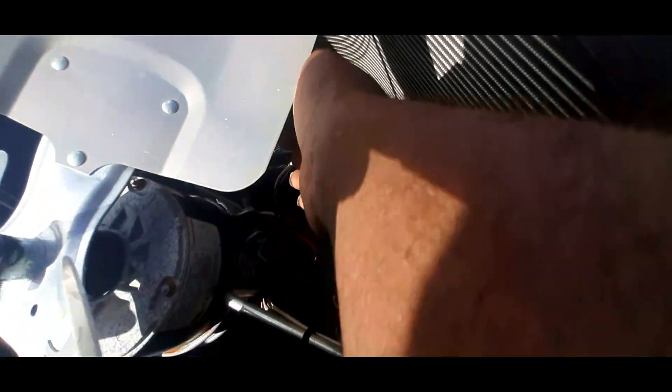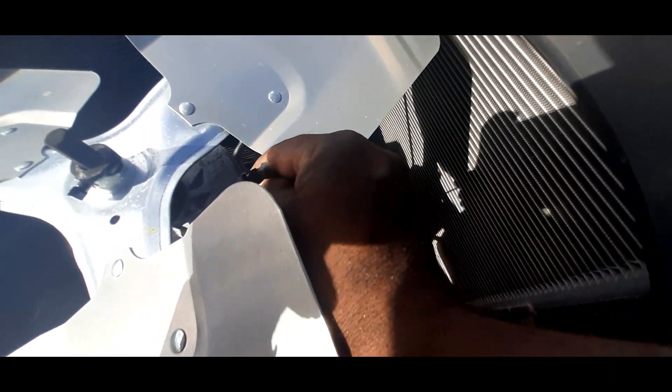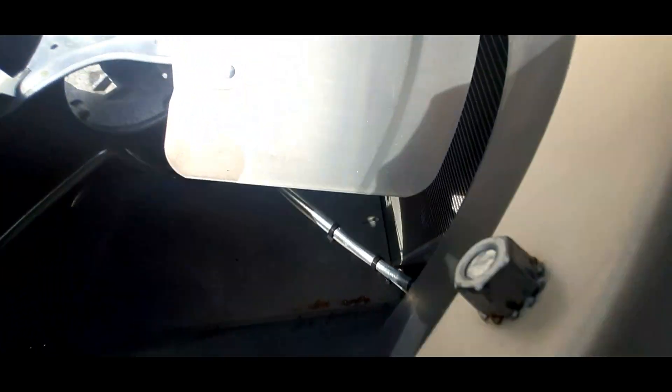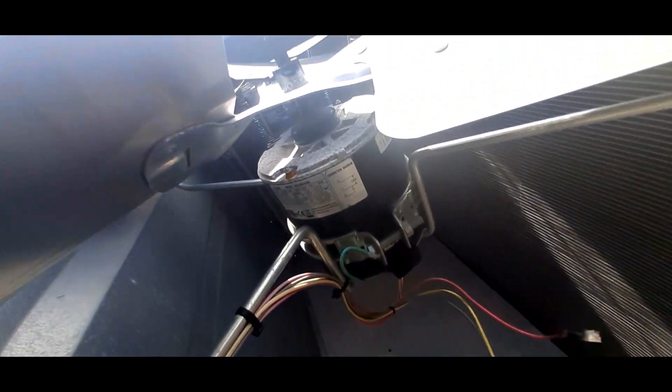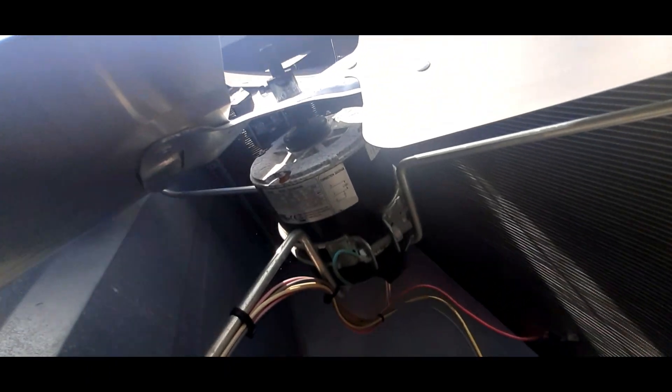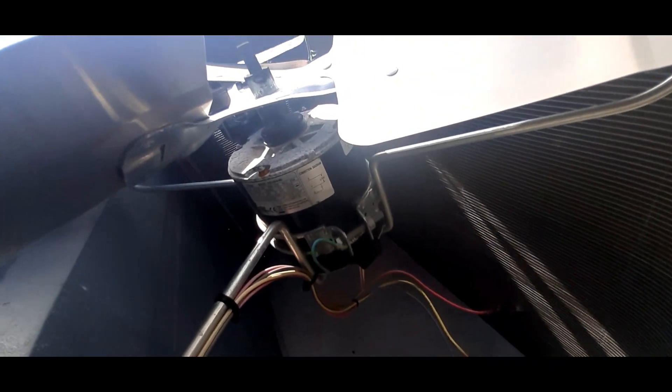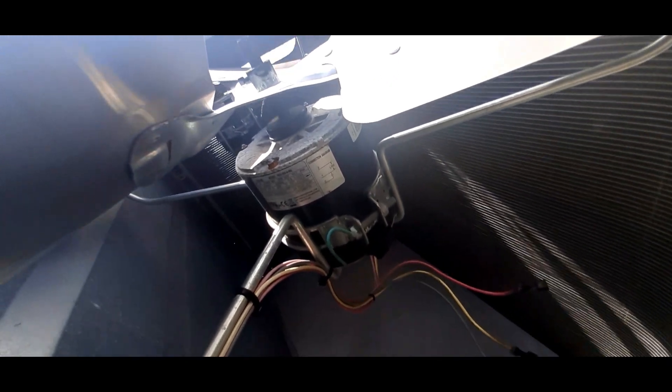It's pretty cool. I don't know if you can see this, but look at this connector, definitely charred. So look at the other one, have some melting going on also. You can see the motor look like it's been overheating, starting to rot the metal. The paint is starting to chip and rust. It's been heating up for some time. So I'm gonna go ahead and get this motor ordered and I'll go from there.